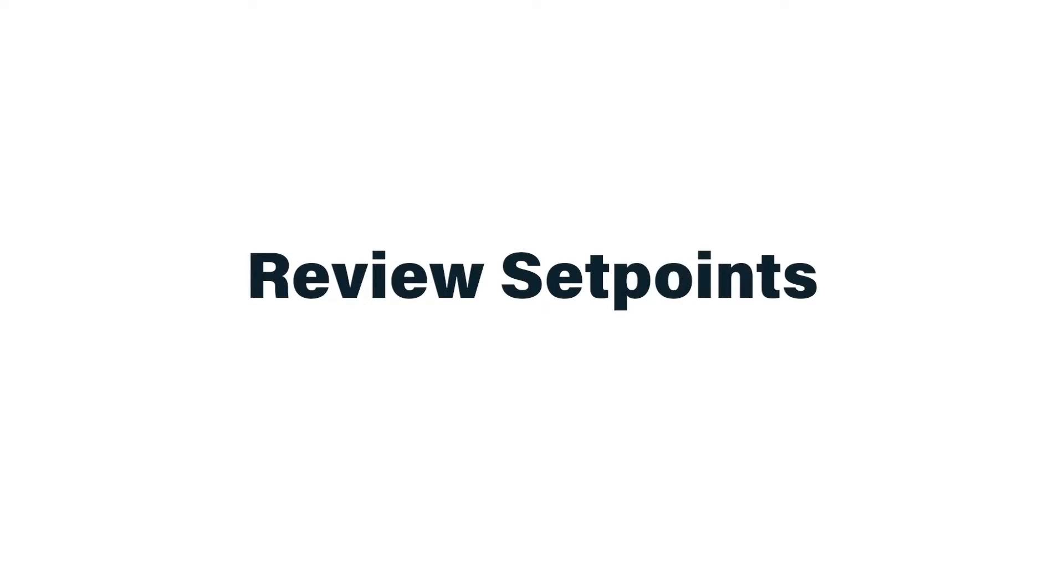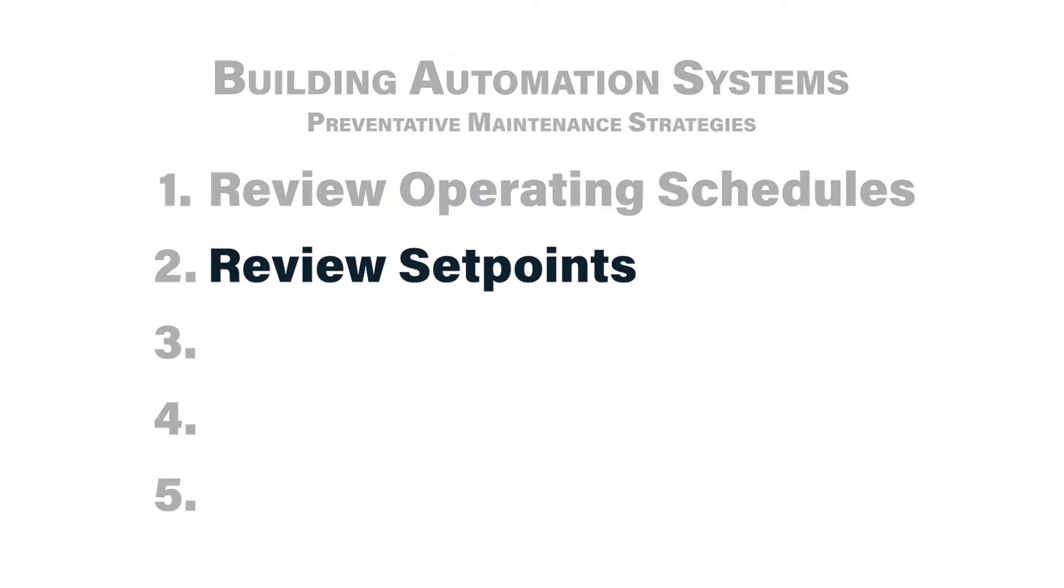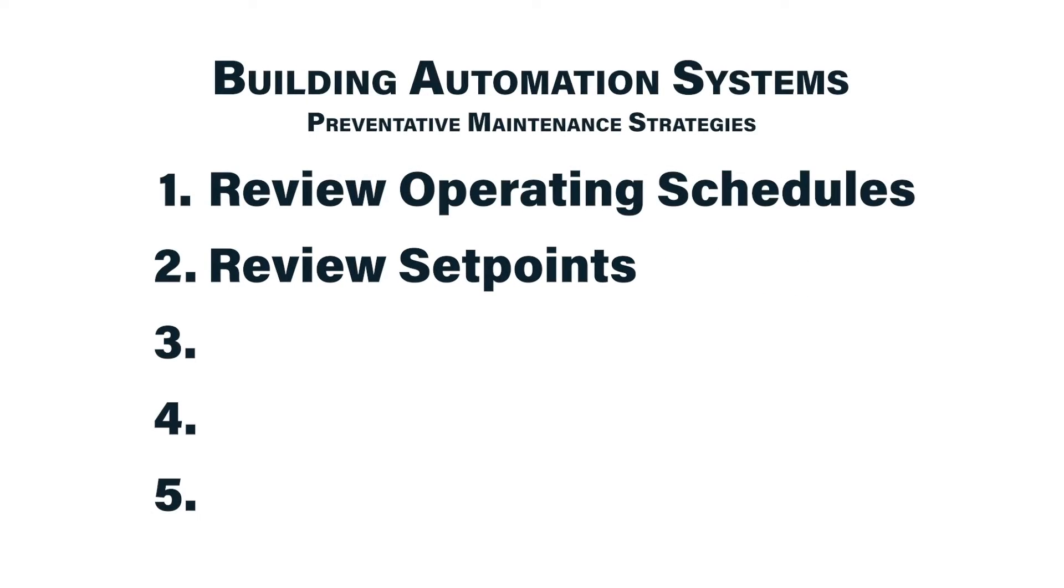Task number two would be to review the set points that your systems are operating at. Do they make sense? These set points are oftentimes adjustable on the user interface of the building automation system. And oftentimes set points that the systems are operating to get changed to inappropriate values.